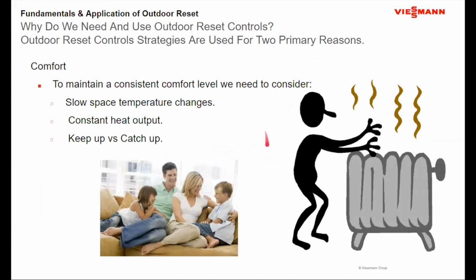Okay. If I want a building to be comfortable, the building is much more comfortable if there's a constant input of energy into the building, providing for a fixed temperature, rather than pulsing the building periodically with the maximum amount of heat that the heat emitter can put out. So it's all about maintaining comfort. It gives me nice slow temperature changes. I'm not pulsing it with the full output of the heat emitters. It's a constant heat into the building. Think of it as keep up versus catch up. So from the aspect of performance and comfort, that becomes one of the driving factors behind doing outdoor reset.